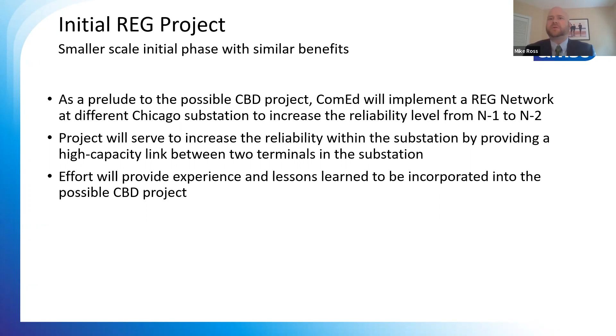So within this one fenced area in northern Chicago, there are two substations. So thinking of the downtown area where there are 3 separate substations serving that portion, in this one fenced area, there are 2 substations, one on the north side or the top right-hand side and one on the bottom left-hand side. And so what we've done is we've taken a superconductor cable at 12 kV and we've interconnected the 2 substations in this one fenced area together so that in the event that they have a problem on one side or the other, they can rely on the superconductor cable to move power across.